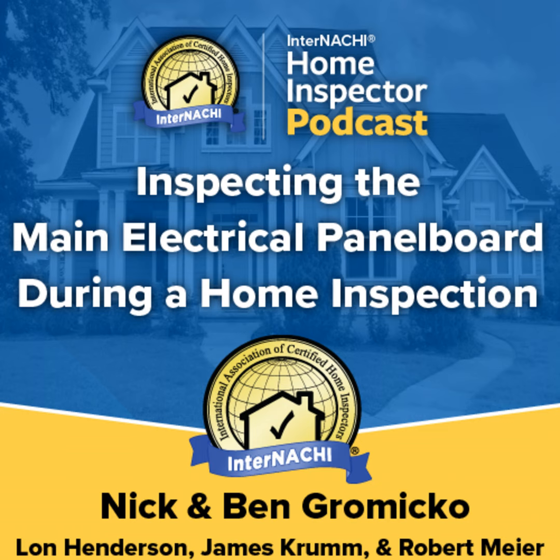For example, a newly installed panel board should be covered when the electrical contractor is installing the rough wiring above the electrical panel board. Otherwise, the unprotected panel board and its components could be covered with dust and debris. Another example could be when the panel board is installed and the drywall contractor uses a router to cut openings for electrical boxes or fixtures. The drywall dust could enter the uncovered panel board.